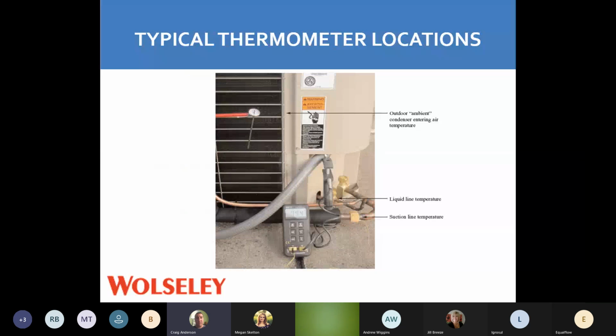So typical thermometer location. The best ones are the clamp-on thermometers. You can buy the accessory to go into your meter, or you can buy a kit that has just clamp-on thermometers. With clamp-on thermometers, we're getting the whole surface of the copper, and it's getting us a better reading. If you don't have clamp-on thermometers, we need some pocket thermometers then. So you want to take this pocket thermometer and get it in, because you want to be able to see the temperature of your suction line and your liquid line while the unit is running.